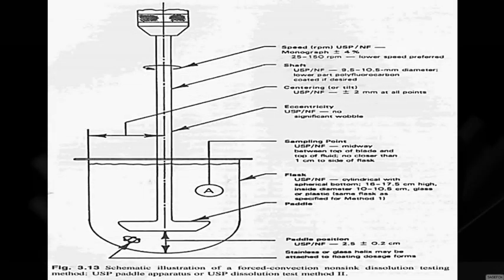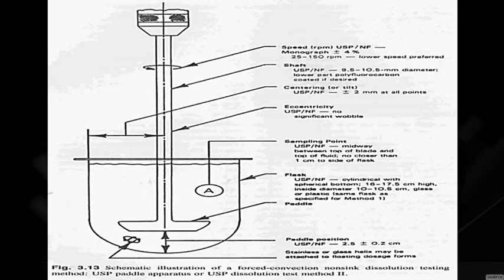USP paddle apparatus (Apparatus 2): speed according to USP NF is 25 to 150 rpm, lower speed preferred. Shaft diameter is 9.5 to 10.5 mm; lower part may be polytetrafluorocarbon-coated if desired. Centering: axis of shaft and vessel must be within ±2 mm at all points. Sampling point: midway between top of the blade and top of the fluid, not closer than 1 cm to the side of the flask. Inside flask diameter is 10 to 10.5 cm. Paddle is positioned 2.5 ± 0.2 cm above the bottom. A stainless steel or glass helix may be attached to floating dosage forms.